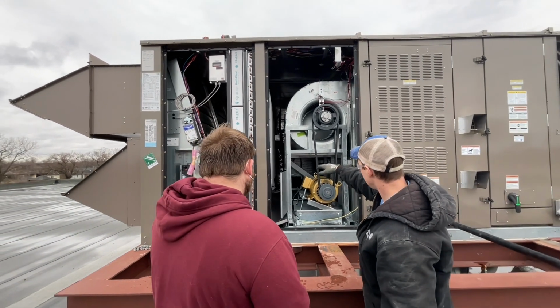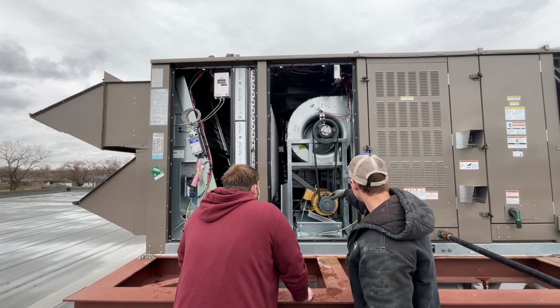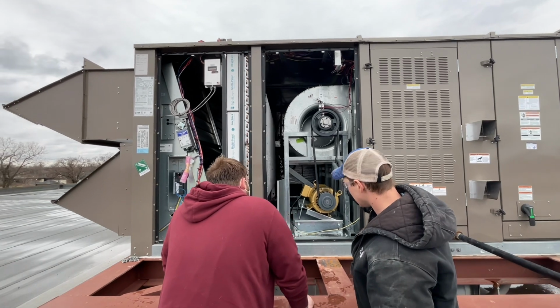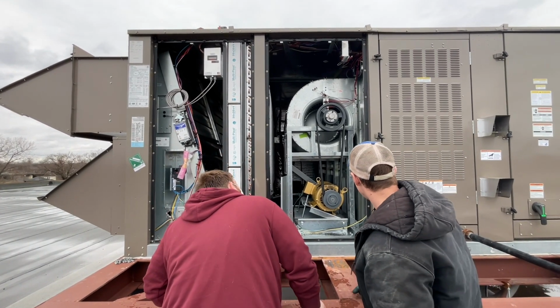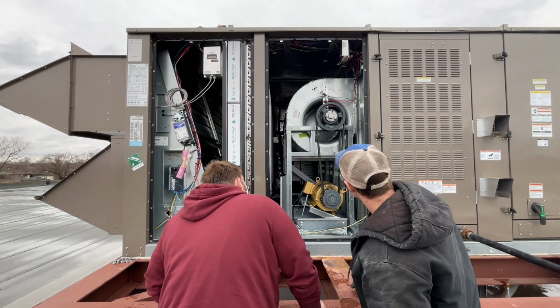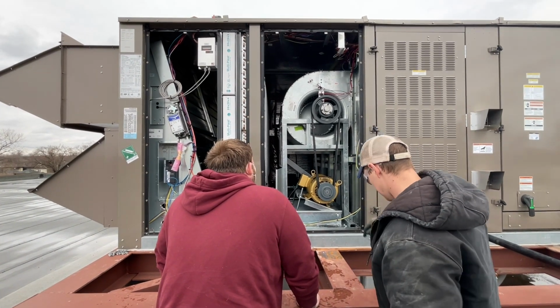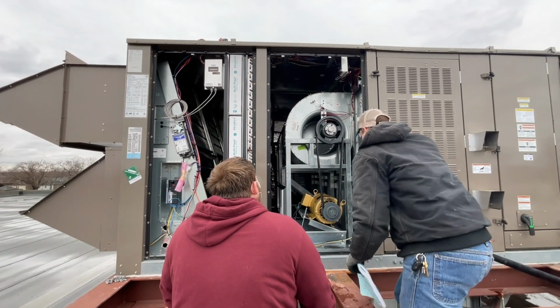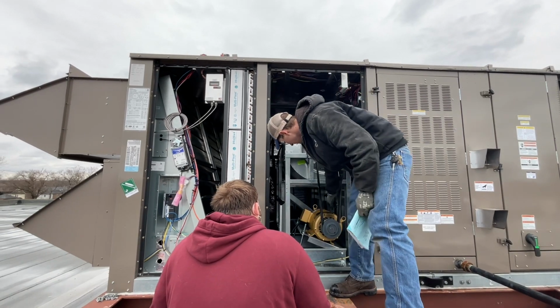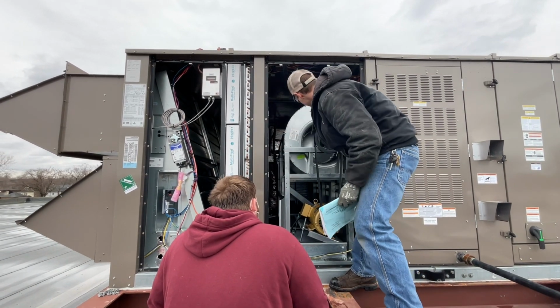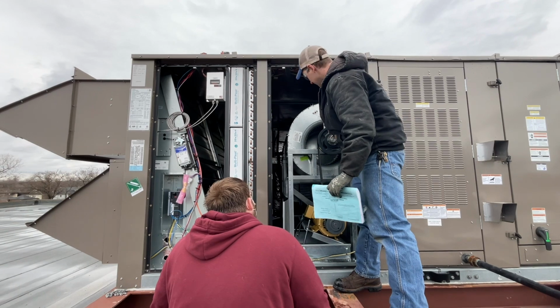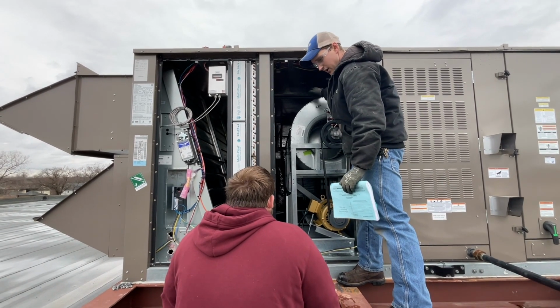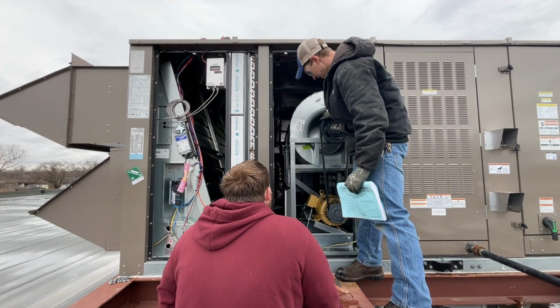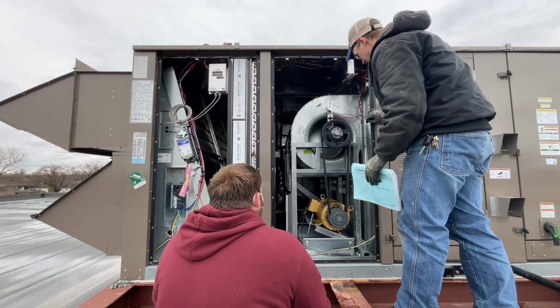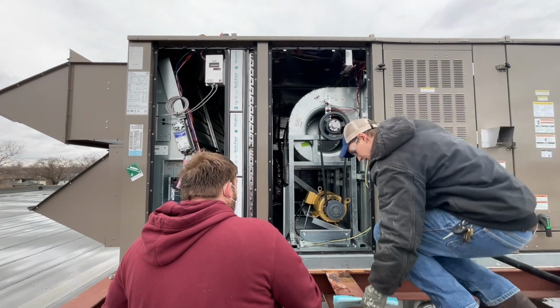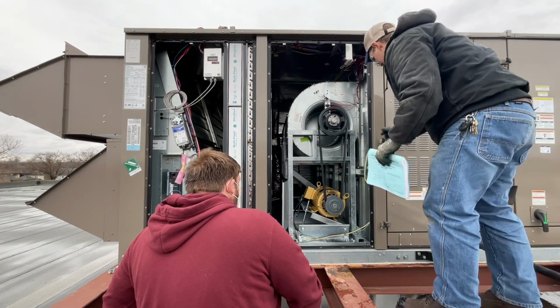Here we got the lower section of the motor belts. So belts, just like your other units, you have to change those. Tension them up. We have grease fittings. There's 4 grease fittings. 2 on the motor. We have a grease fitting here, a grease fitting here. Grease fitting right up here for the fan shaft, and then on the other side, if you take that door off, there's another grease fitting for the fan shaft up there. So belts, grease, that's another maintenance item. You'll have to keep on top of it.